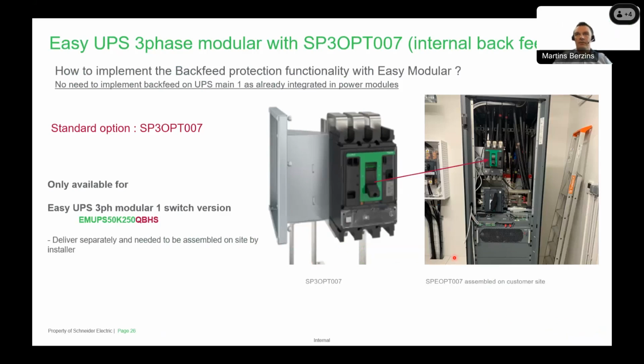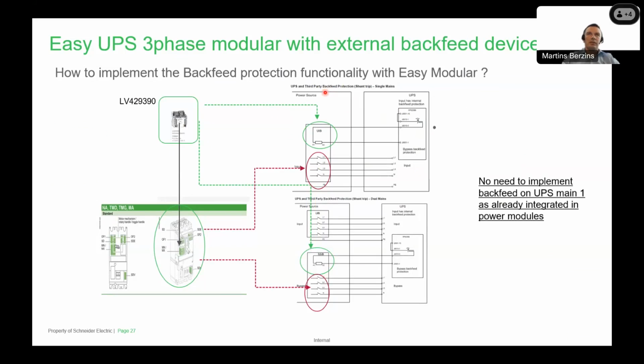About the internal backfeed kit, here is how it looks. It's available as a standard option for the 1-switch version, and it's delivered separately and needs to be assembled on site by the installer. As I mentioned, for the 4-switch version we don't have such an internal kit, due to the space restrictions inside the UPS. For that reason, the customer can use third-party external backfeed protection circuits. Basically, you can install the breaker and the coil in the electrical panel, and ensure this backfeed protection for the single mains or dual mains connections.